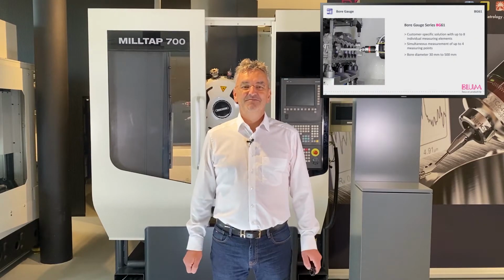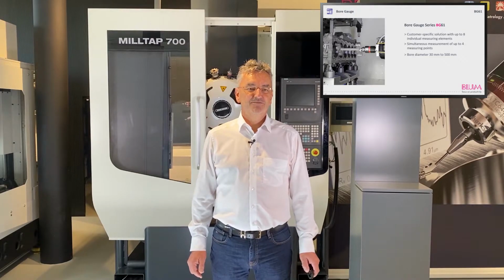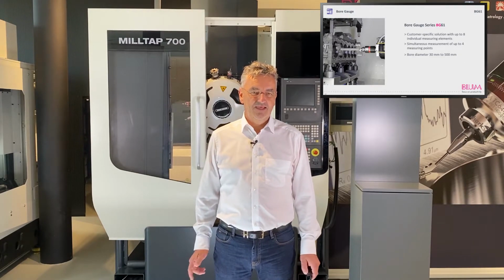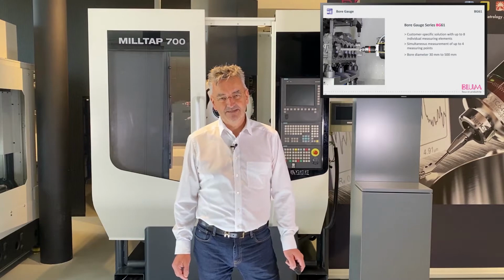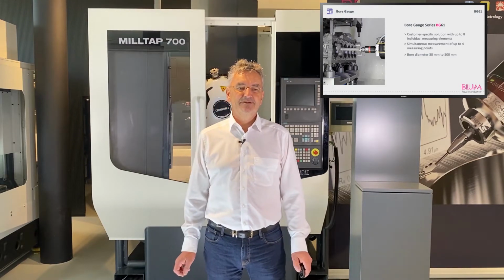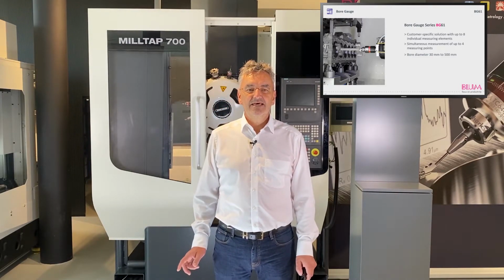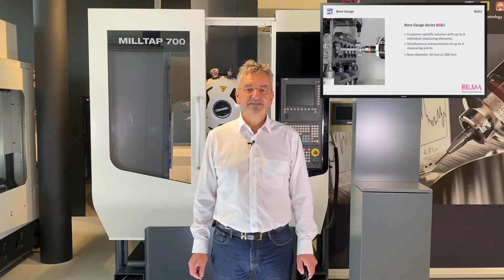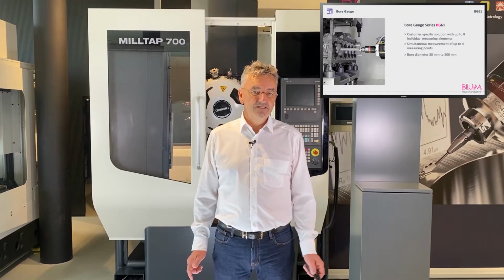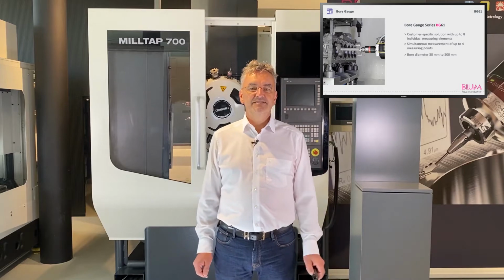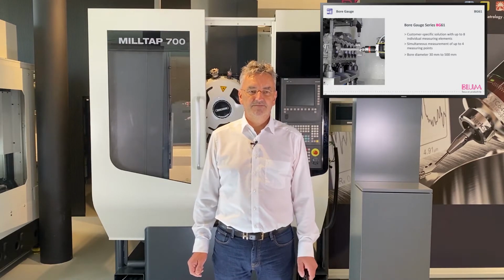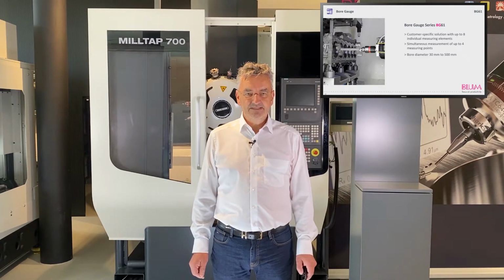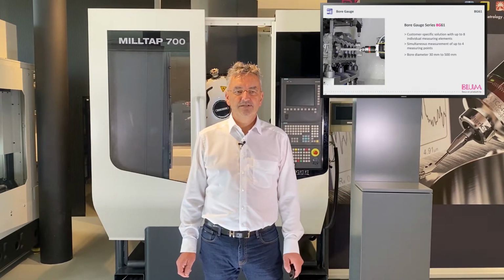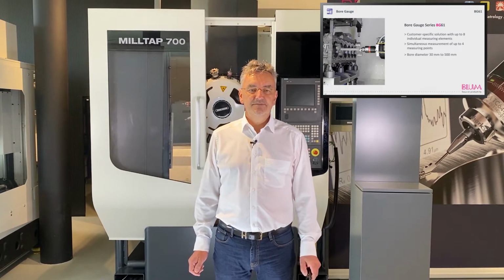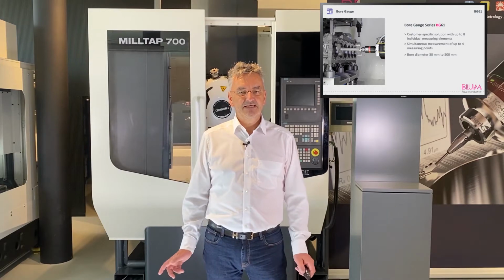I'd now like to present an alternative bore gauge design. It's the BG61, a system that operates with single measuring elements. Up to 8 of these single elements can be installed on the gauge. This allows you to measure, for example, 4 diameters in parallel. The BG61 can also be used to detect large bore diameters where the drive needle principle of the BG60 reaches its limits. Variants measuring 30 mm in diameter up to several hundred millimeters are possible.